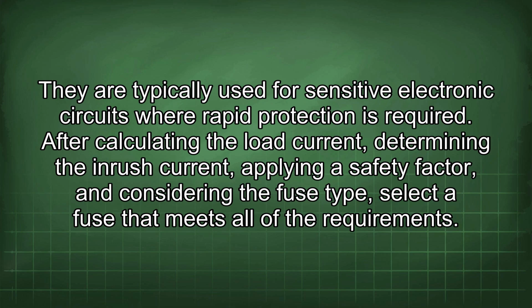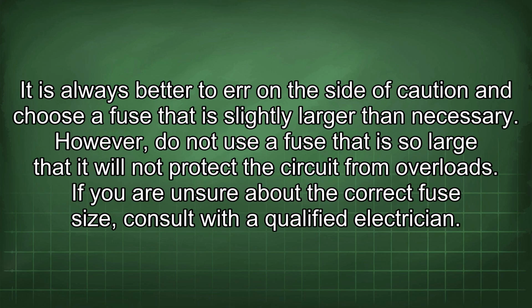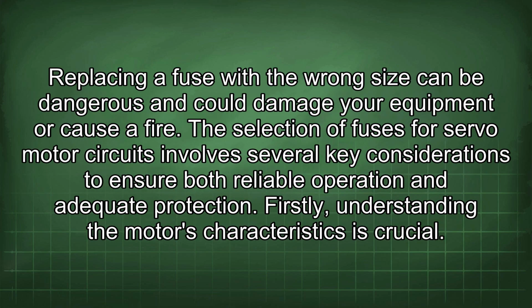After calculating the load current, determining the inrush current, applying a safety factor, and considering the fuse type, select a fuse that meets all of the requirements. It is always better to err on the side of caution and choose a fuse that is slightly larger than necessary. However, do not use a fuse that is so large that it will not protect the circuit from overloads. If you are unsure about the correct fuse size, consult with a qualified electrician. Replacing a fuse with the wrong size can be dangerous and could damage your equipment or cause a fire.